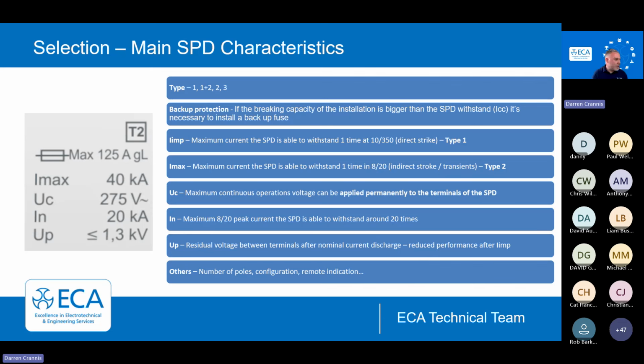We talk about Imax on here. If it was a type 1, it would be what we call Iimp, and that's the maximum withstand it can take, one time. So if we had a 40 kA incident, this SPD is done. It's done its job. It only has to do that once, and it will do it once alone, whether that be for lightning on a type 1 or it would be for indirects on a type 2. 40 kA is the maximum impulse it can take out one time.